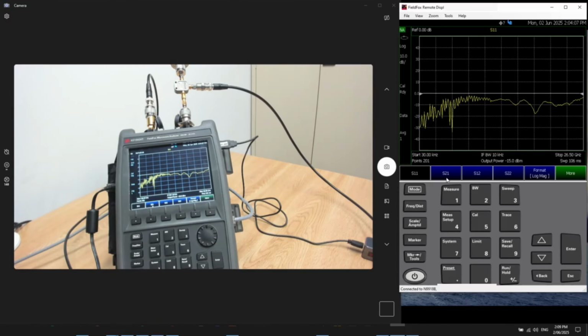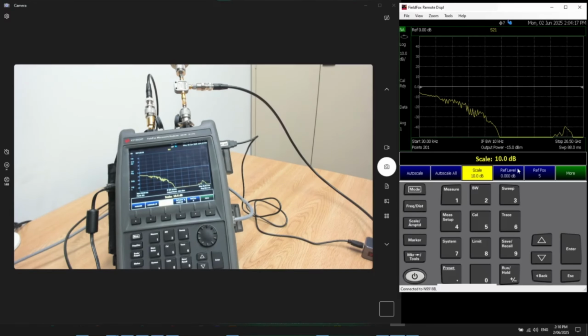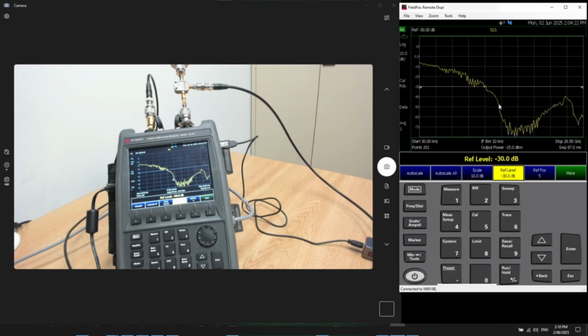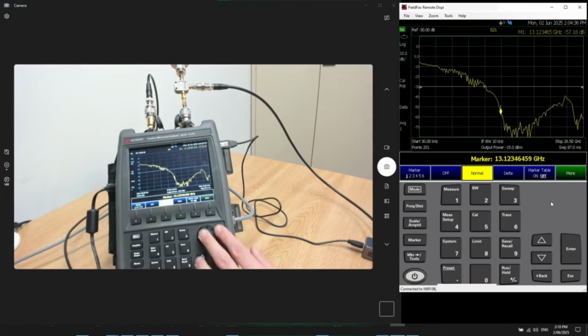So let's go step by step on how to set up the FieldFox to what we want before you run the calibrations. We need an S21 measurement, and as you can see here, the cable response is very bad, somewhere right in the middle of the screen. In fact, it's starting to deteriorate much from this point. Let's turn on the marker and see what it's all about. The safe region is somewhere here, up to 3 gig, and I'm going to turn on another marker. You can see that here it is fluctuating and it's really bad. So we can probably stop at about 10 gig-ish. 10 gig, 0.2, 3 gig at 0.1.